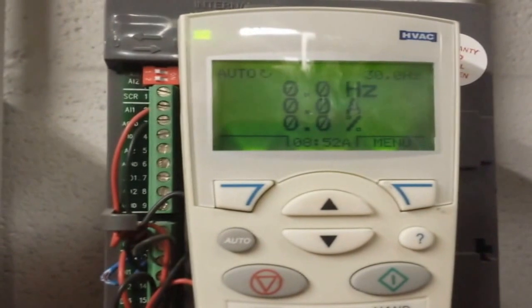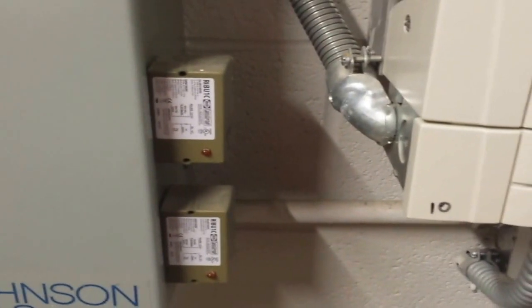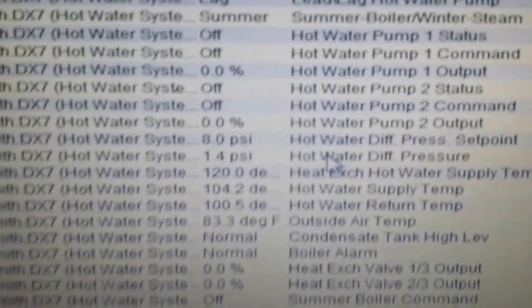You can see currently, because I have this drive disabled for demonstration purposes, we have a 0% on the input. We also have 0 Hz going out from this drive — that's because we're disabled. The relay is open; there is no relay contact closed, it's just a set of dry contacts. But once that relay closes, that is the run enable for this drive. The drive will then look for a speed reference coming from the controller and ramp up the motor. Currently I have this system completely disabled — reference for the pumps are off, and the speed reference is at zero.